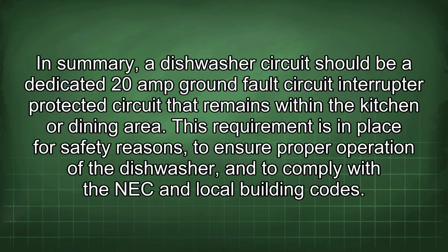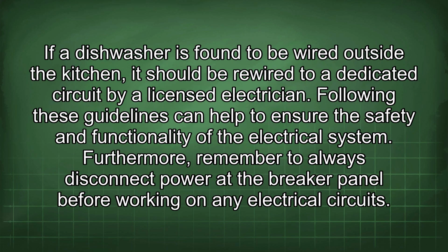In summary, a dishwasher circuit should be a dedicated 20 amp ground fault circuit interrupter protected circuit that remains within the kitchen or dining area. This requirement is in place for safety reasons, to ensure proper operation of the dishwasher and to comply with the NEC and local building codes. If a dishwasher is found to be wired outside the kitchen, it should be rewired to a dedicated circuit by a licensed electrician. Following these guidelines can help to ensure the safety and functionality of the electrical system.